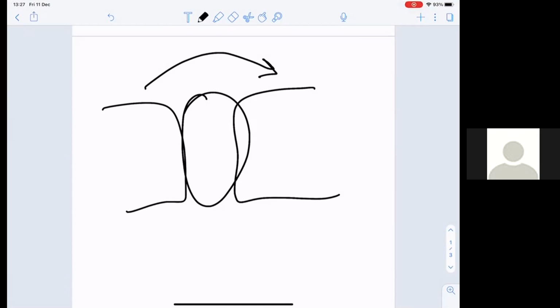Because they'll get induced. If you induce a current and there's a risk that it will go through the patient to earth, then there's a risk of shock. And they both have to be connected to earth, don't they? I think for the patient it has to be connected to earth to create a circuit. I'm not sure if the other current does. I'm not sure. That makes some sense.